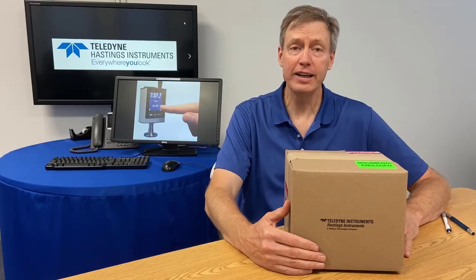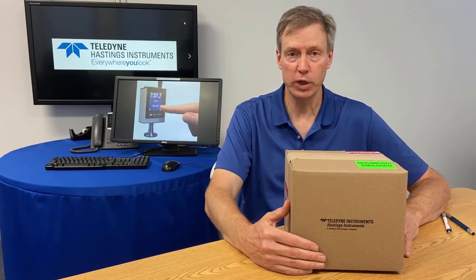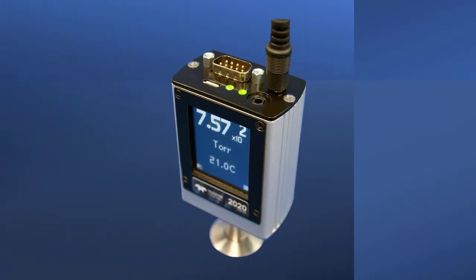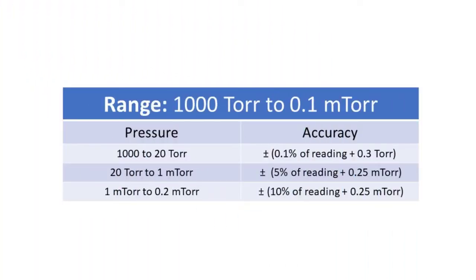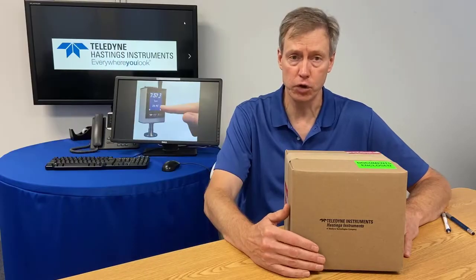And to get started, I'd like to briefly describe the HVG-2020B. The HVG-2020B is a dual-sensor vacuum gauge that measures from just above atmospheric pressure down to 0.1 millitorr. Two sensors are used.